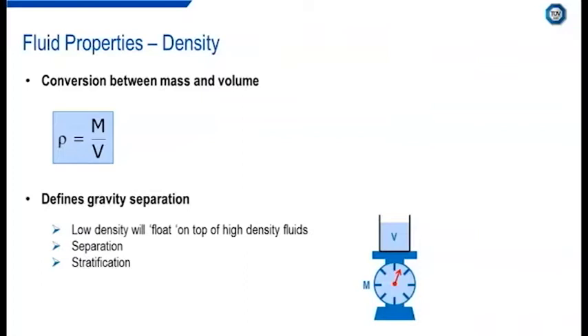The thermophysical properties of the fluid being measured are vitally important for flow measurement. Knowing the fluid density allows conversion between mass and volume. The majority of flow metering technologies measure volumetric flow, and therefore converting to mass, knowing the fluid density, is critical.